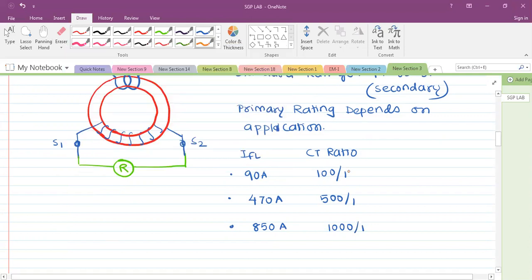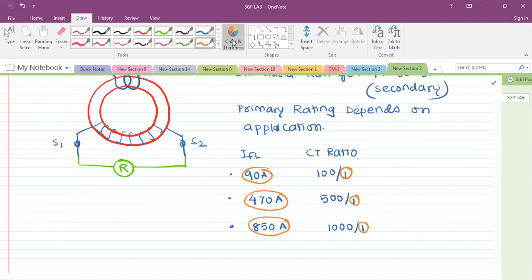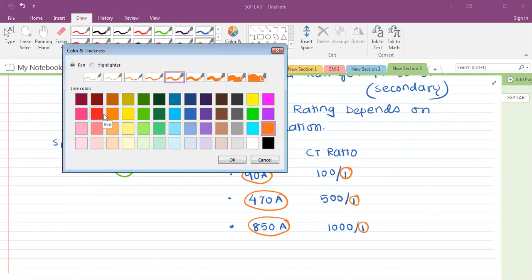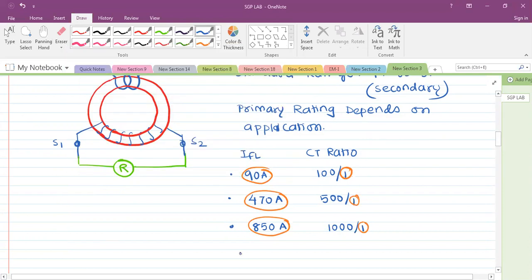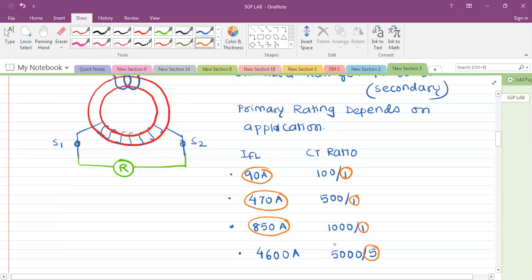So what do you see here? The secondary rating is always 1 ampere, however the primary rating depends on your application. For example, if the application has a current around 4000 to 4600 ampere, then you will select a 5000 bar 5 CT. Generally, bar 5 is used when the primary current is high.